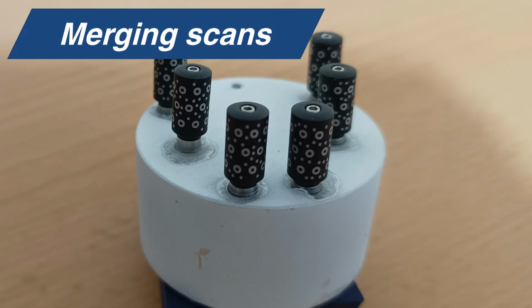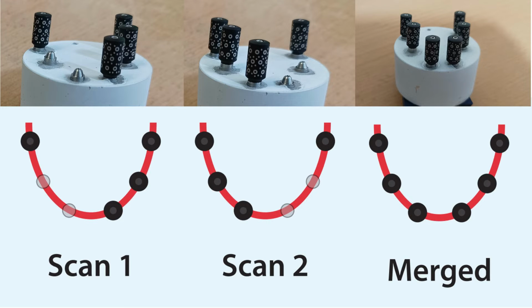Let's pretend that these posts are too crowded to scan in one go, or we have more than 6 implants to scan in one jaw. What we can do is make 2 scans and then merge them together. So in this example, we are going to shoot scan 1, then swap over the positions of some posts, or add more posts, and then do scan 2. But note that we must always leave the positions of two posts unchanged. Then we can merge them.